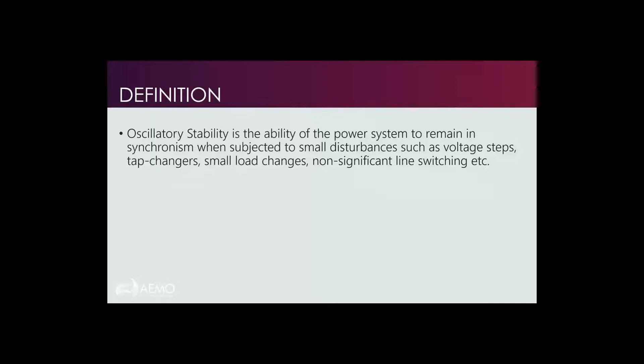The definition of oscillatory stability is the ability of the power system to remain in synchronism when subjected to small disturbances, such as small voltage steps, not faults. Faults would be transient stability. Then tap changes, small load changes, and non-significant line switchings.